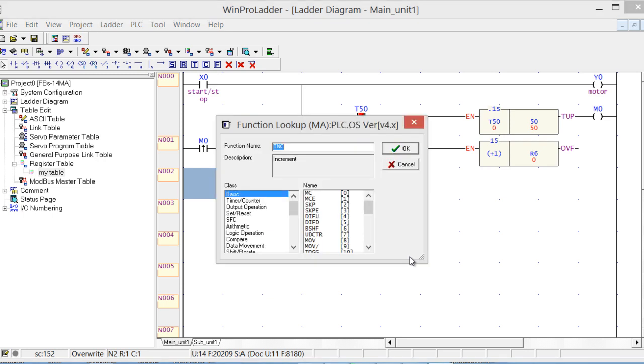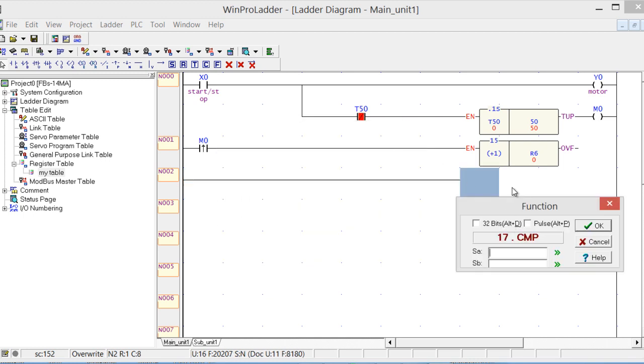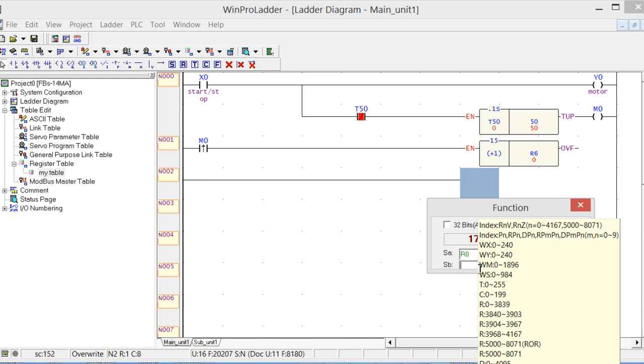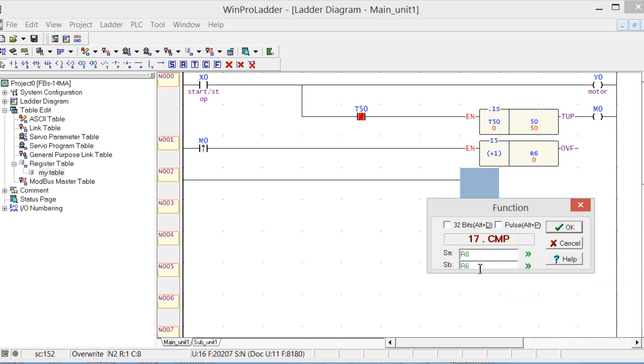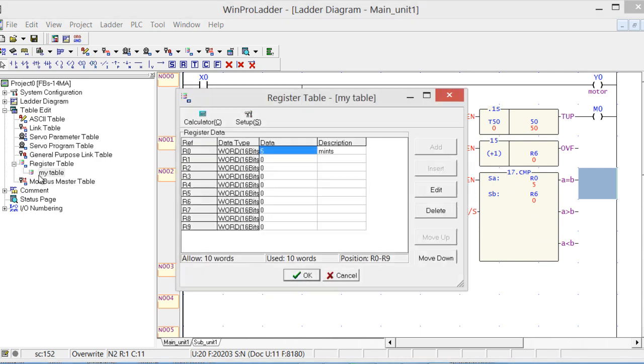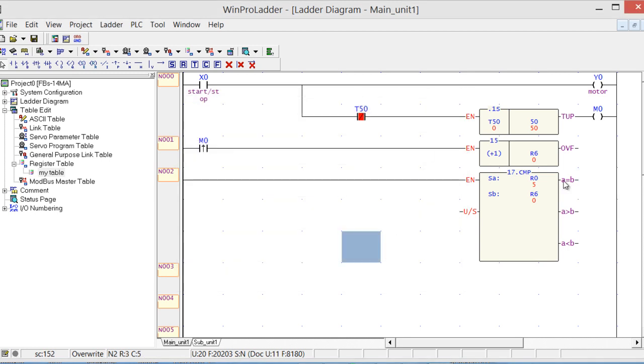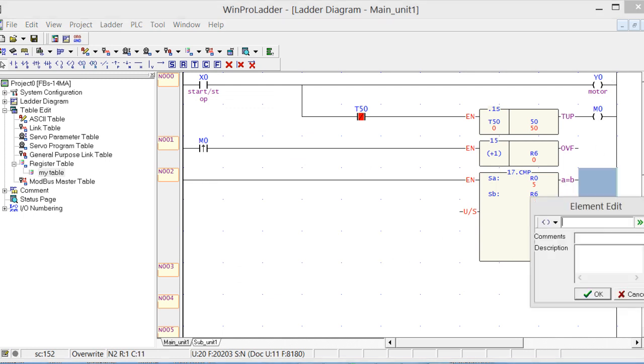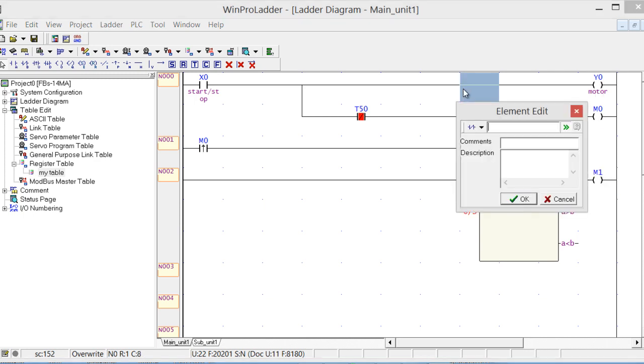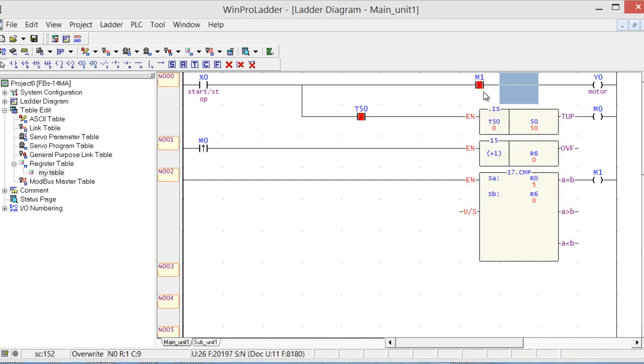We'll need a comparison. What is source A? Source A is R0, and source B is R6. You can see in the table that R0 consists of 5. This value can be changed. When A is equal to B, then what to do? Set high M1. So when M1 gets high, it will turn off. Let's use M1. By default M1 is 0, keep Y0 on, and when it turns on, this instruction will become false so it will turn off.